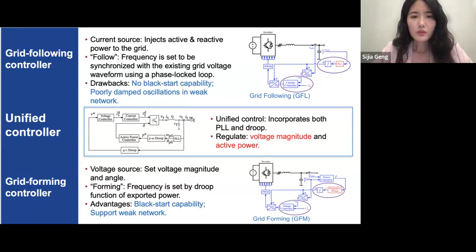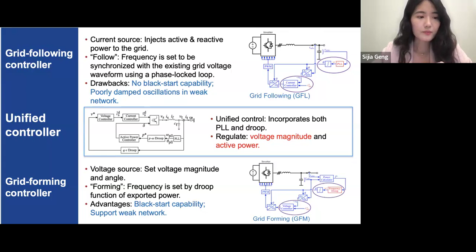In fact, in one of our recent works, we proposed a unified inverter control scheme that incorporates both a PLL and a frequency droop control. As such, it inherits the characteristics of both grid-forming and grid-following inverter controls. It regulates the voltage magnitude and active power at the same time. So in this sense, this unified inverter behaves like a conventional generator.